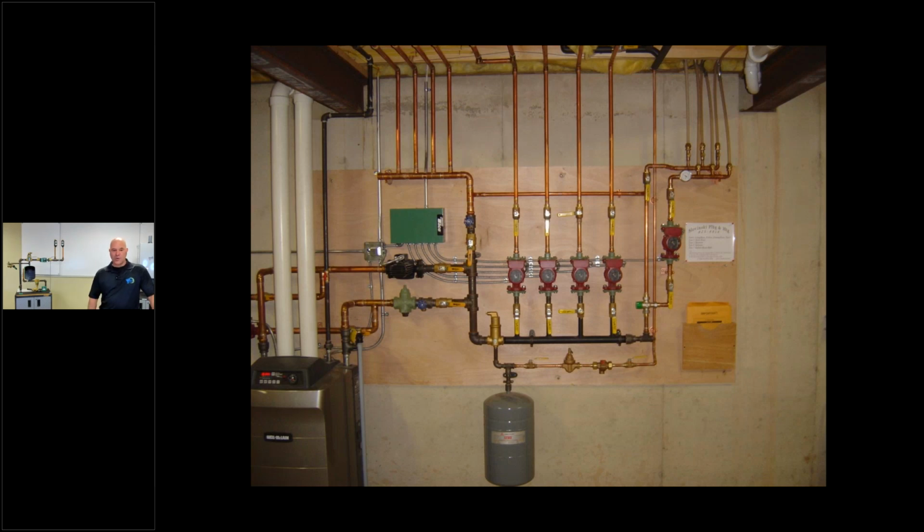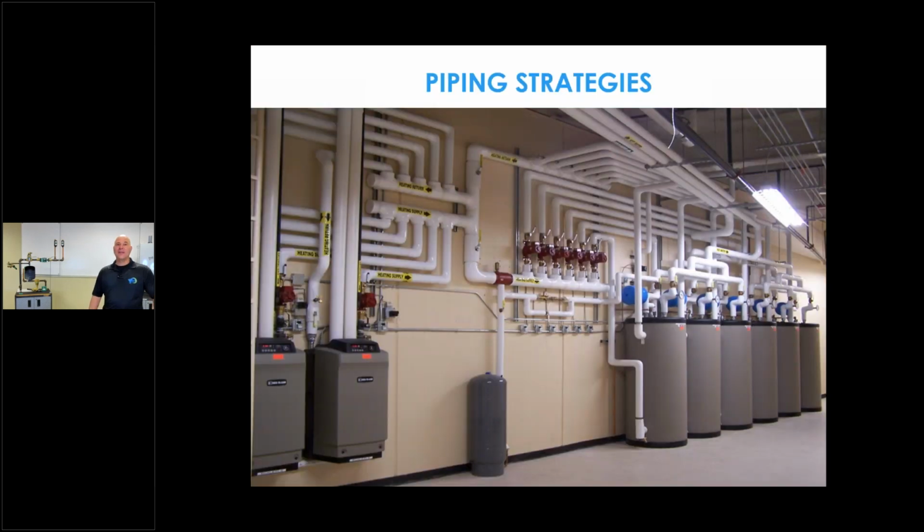Does anybody see anything wrong with that picture? Since we're the Taco guys. Yeah, wrong color pumps. Primary, secondary, boiler into the bowl of the T. Oh, look at that. They used our flanges because they're good. But man, oh man, I got to have some fun with it.